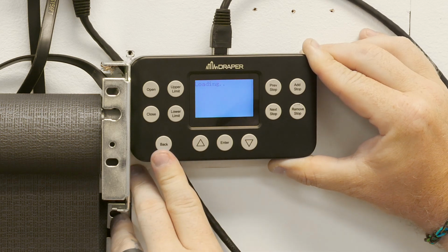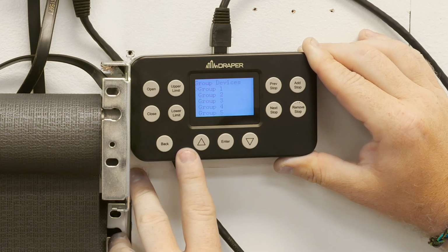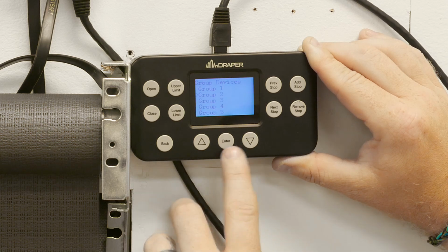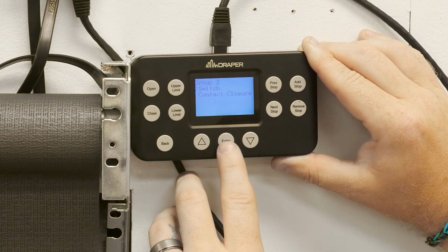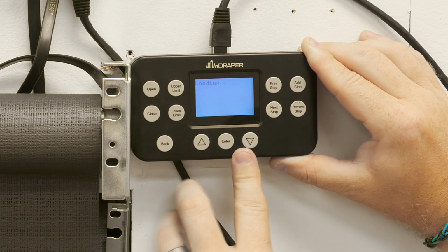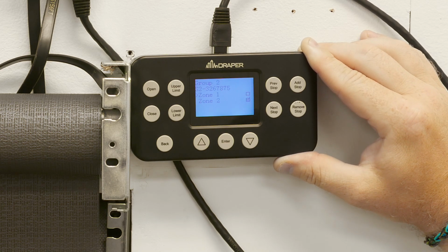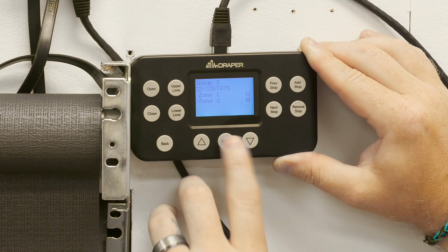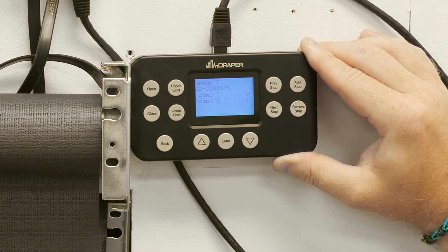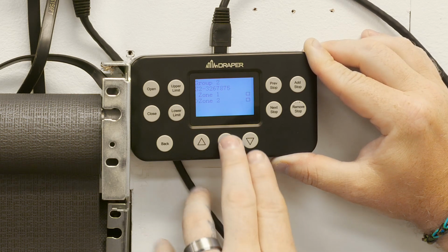So now I'm going to back out. I'm going to go all the way back to my group devices menu. I'm going to go to group 2, hit enter. I'm going to select my switch. Again, I can see that S2 is already highlighted, so I'm going to go in here and I see that group 2 is already assigned to zone 2 of the switch, which is perfect. It's exactly how I wanted it. If for some reason you did not want this programmed this way, I could simply come here, check this, and it unchecks that box. Now zone 2 is not programmed, it's back to a master. But for this instructional video's purposes, I'm going to leave this with zone 2.